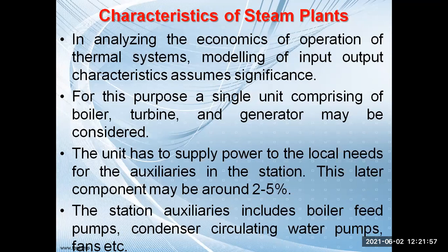Now the unit has to supply power to the local needs for the auxiliaries in the station. This latter component may be around 2 to 5%. See, in the individual unit, the generator will generate power, and that generated power is again reused in the auxiliary components of the power station.